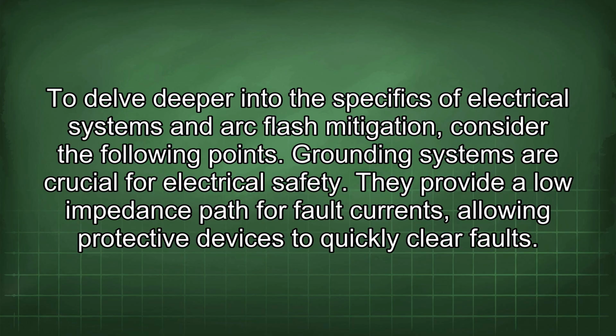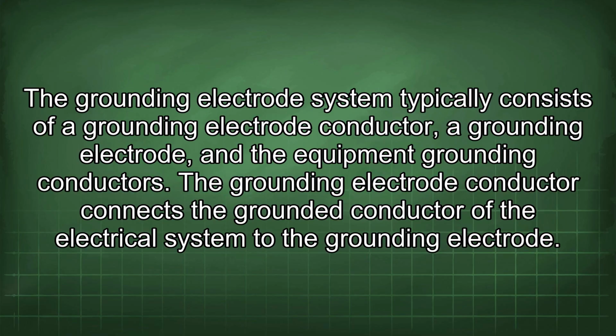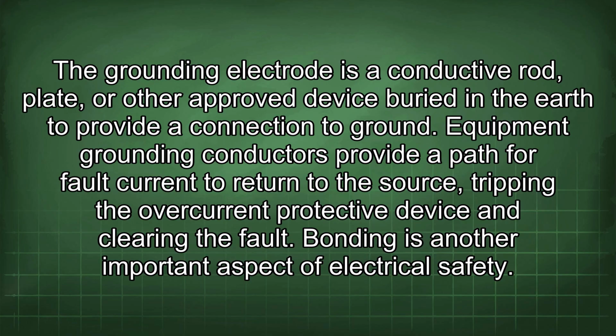To delve deeper into the specifics of electrical systems and arc flash mitigation, consider the following points. Grounding systems are crucial for electrical safety. They provide a low impedance path for fault currents, allowing protective devices to quickly clear faults. The grounding electrode system typically consists of a grounding electrode conductor, a grounding electrode, and the equipment grounding conductors. The grounding electrode conductor connects the grounded conductor of the electrical system to the grounding electrode. The grounding electrode is a conductive rod, plate, or other approved device buried in the earth to provide a connection to ground. Equipment grounding conductors provide a path for fault current to return to the source, tripping the overcurrent protective device and clearing the fault.